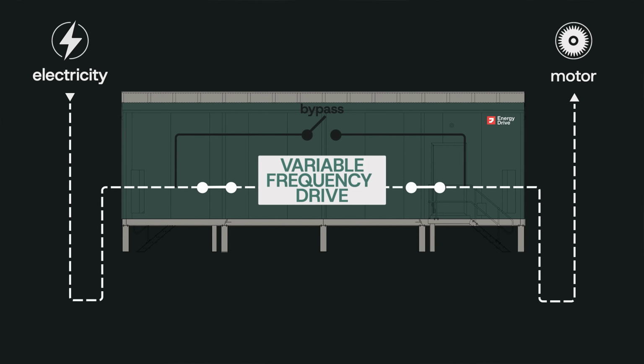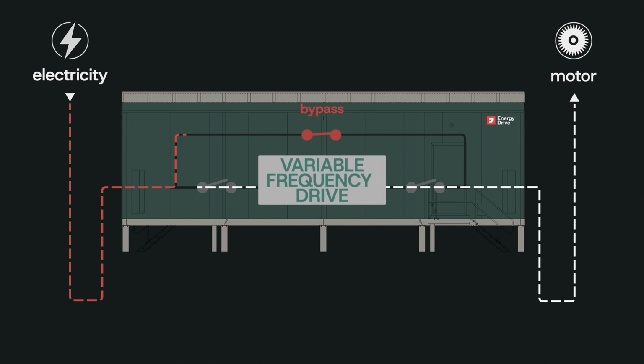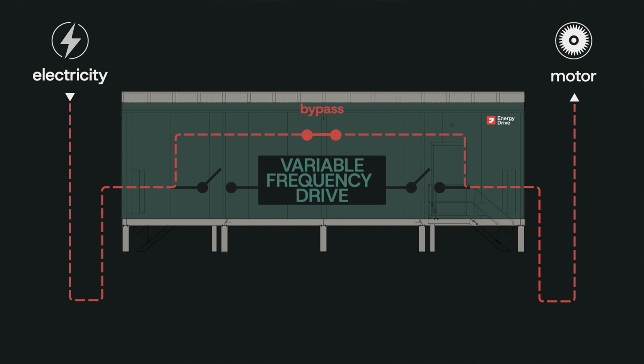We at Energy Drive mitigate this largely by installing bypass systems. Should something go wrong with the VFD, we'll very quickly be able to return the plant back to its operation identical to before the VFD was installed. Effectively, we electrically remove the VFD and the plant continues to run as though we'd never been installed.